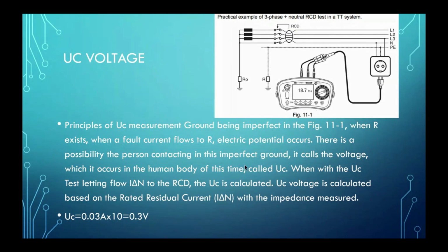So how do we calculate this UC voltage? It uses the rated residual current, meaning your RCD rated current times the impedance measured. Normally we get a result lower than 50. Later I'll explain why it's lower than 50. If higher than 50, your instrument will show something here. So just note this, UC voltage. Later I will go and run the test.